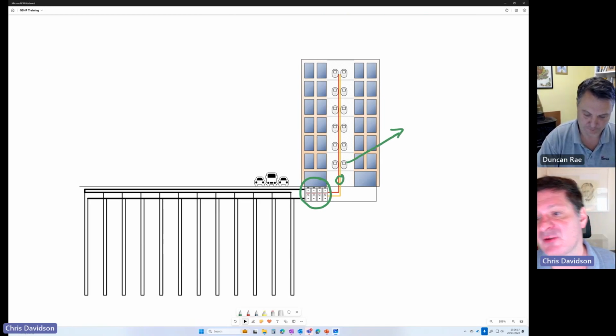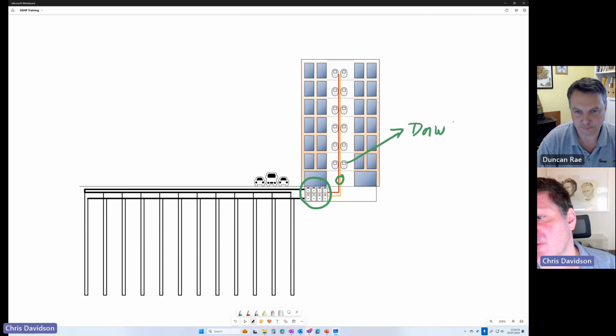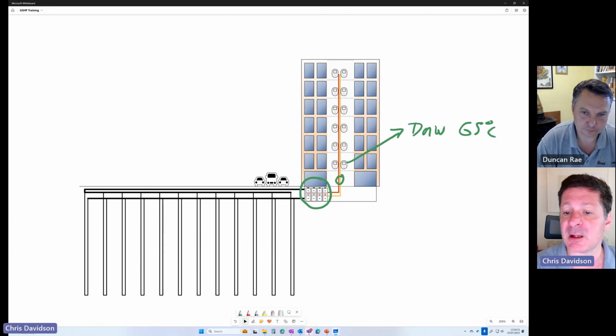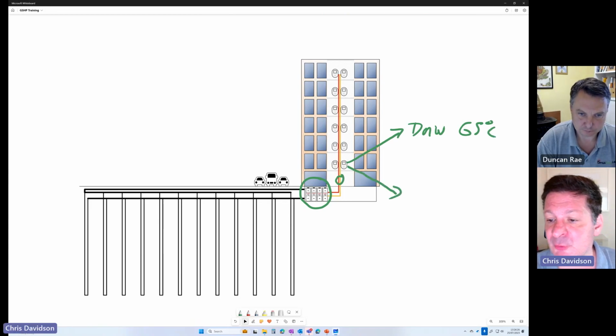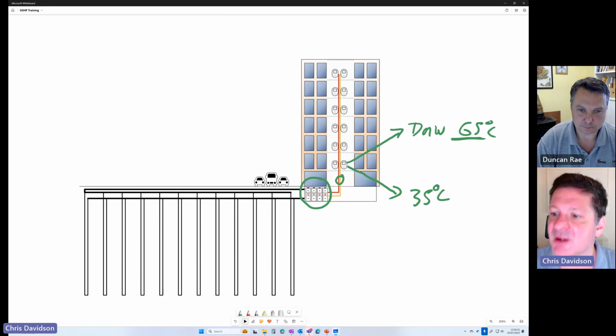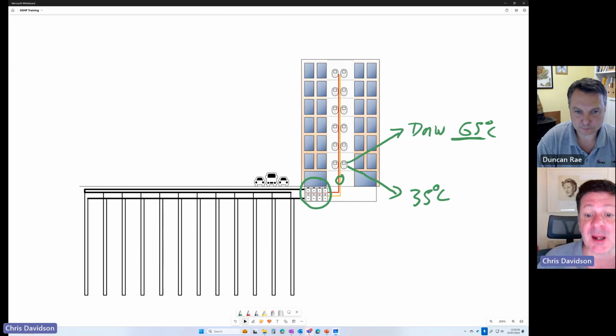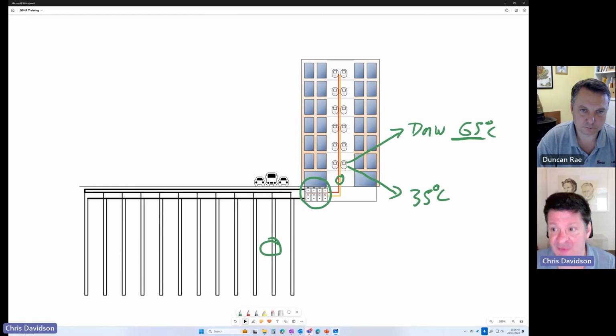Now these heat interface units will be delivering, say, domestic hot water at, let's say, 65 degrees C, could be lower. And it could be doing space heating as low as 35 degrees C. But because we've only got one riser, we'll have to run at that higher temperature to deliver that domestic hot water. And the key thing about heat pumps is the bigger the temperature difference, the bigger the lift between the source down here in the ground and the load, the more electrical consumption it's going to make. So it's going to be less efficient.